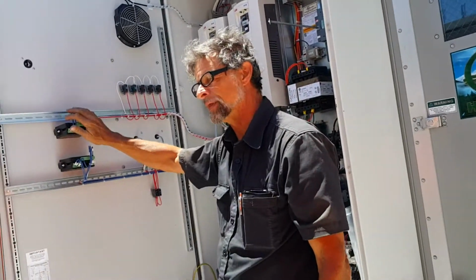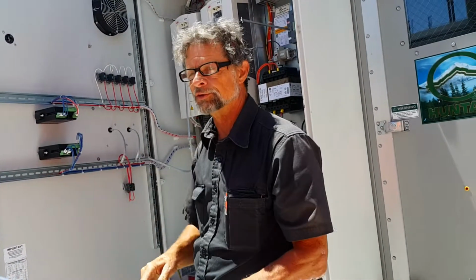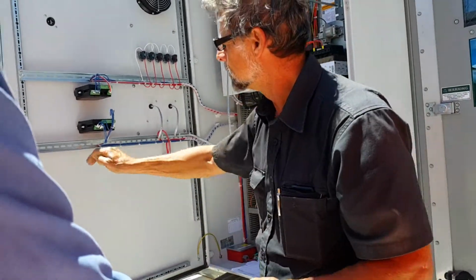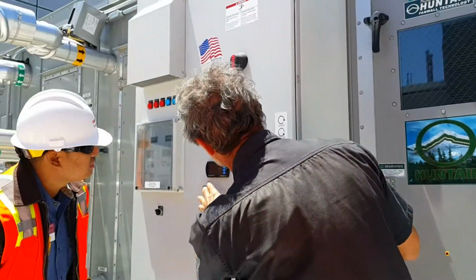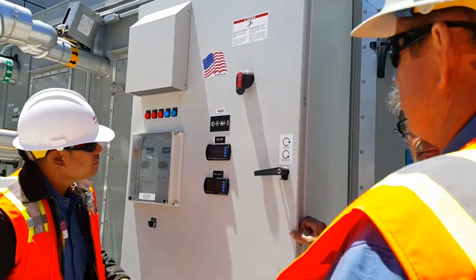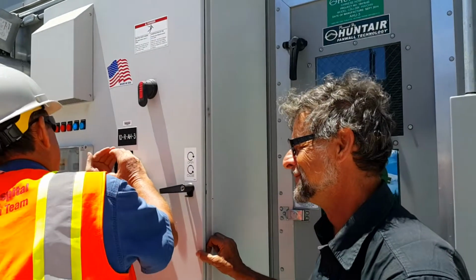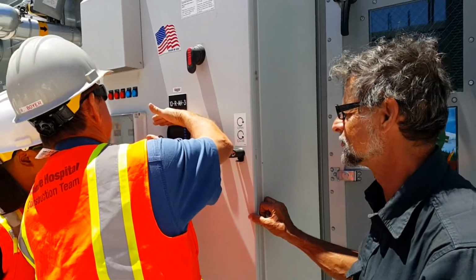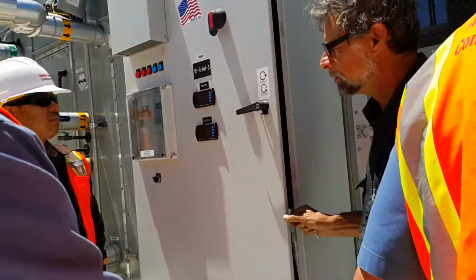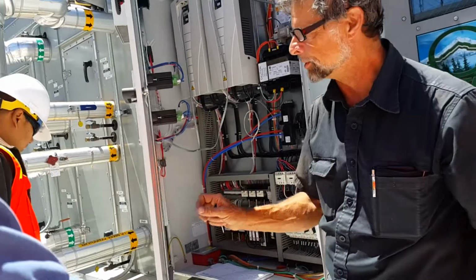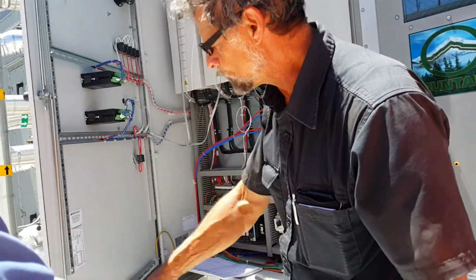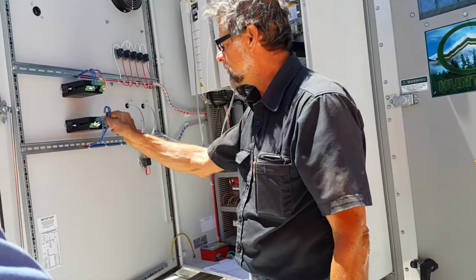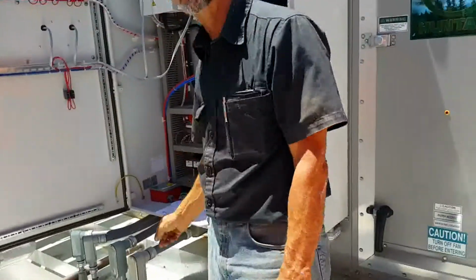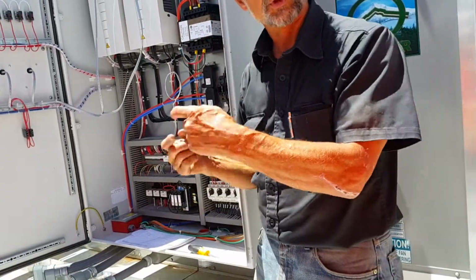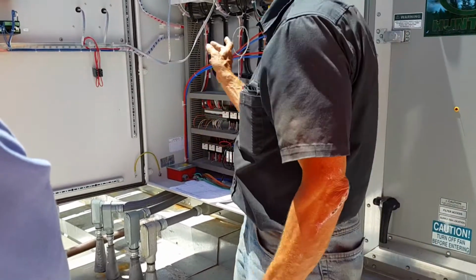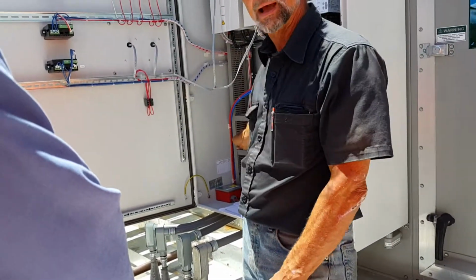This is programmed to accept that milliamp signal and convert it to a CFM count. So that's why you see airflows here. That's actually CFM, pressure diff, one pressure. Well, or is it supposed to be reading CFM? Yeah. And it's probably on a linear scale, and you know nothing's ever perfectly linear. But it also comes back. One of these sets here also comes back to a set of contacts here. Those contacts are supposed to pick that up. So whatever the milliamp signal is here, he gets copied back here on the terminals.